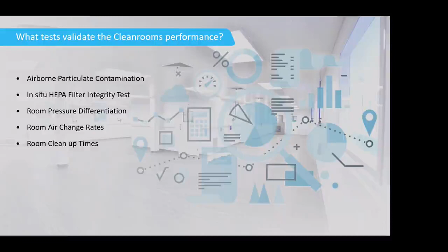So they're done on 5 key parameters. The first is counting the particles. The next is to make sure that the HEPA filter that's been installed is doing its job. After that, we check room pressures to make sure that air is being flushed from high pressure to low pressure areas. We look at the air change rate and we look at the clean-up times.